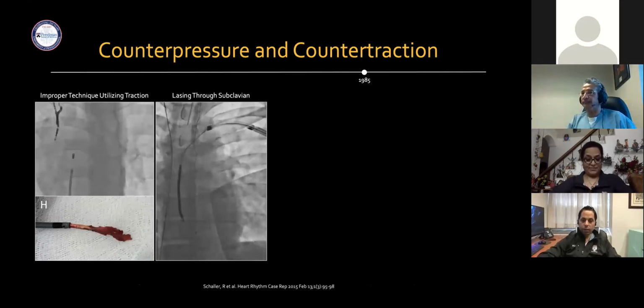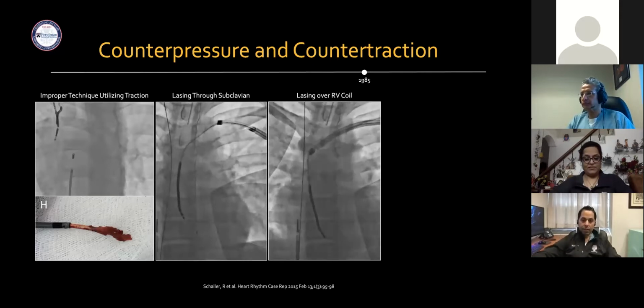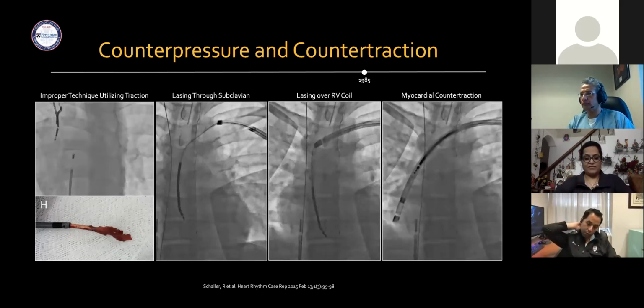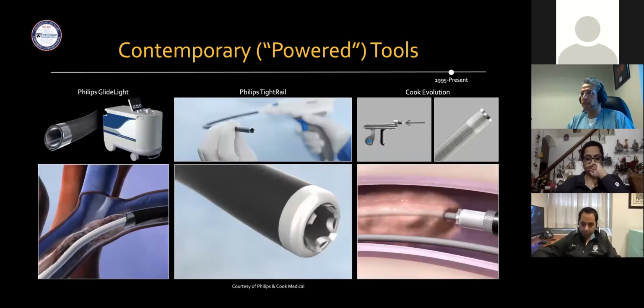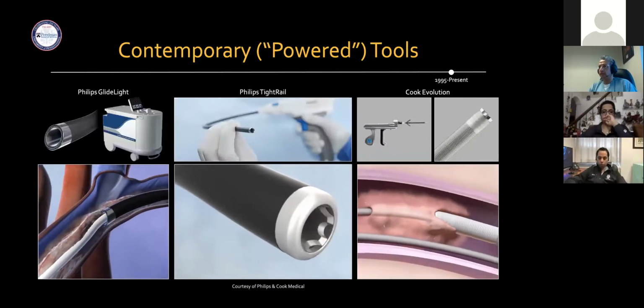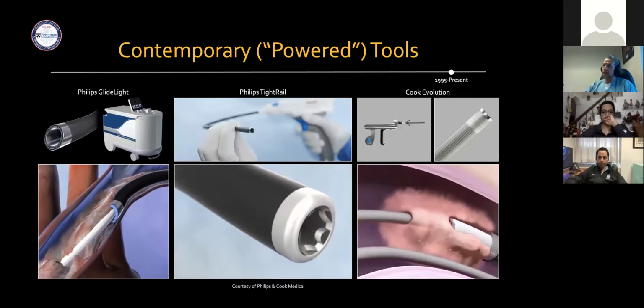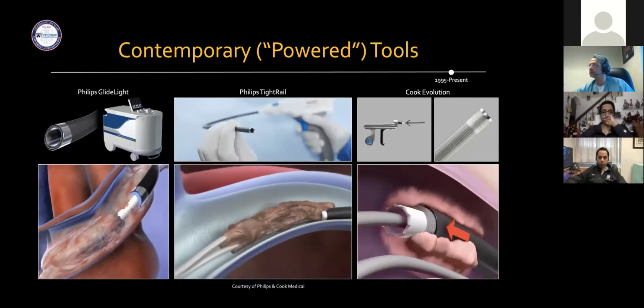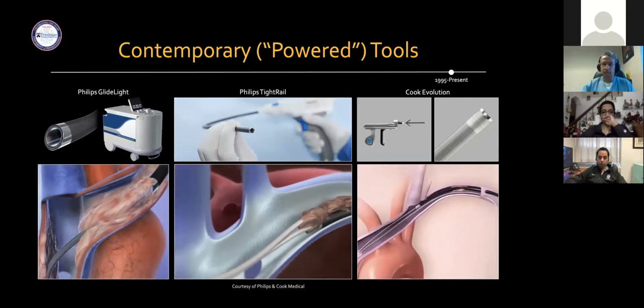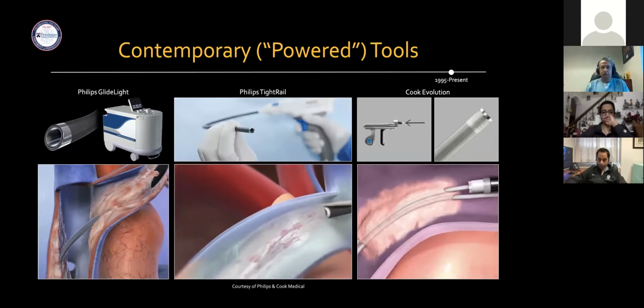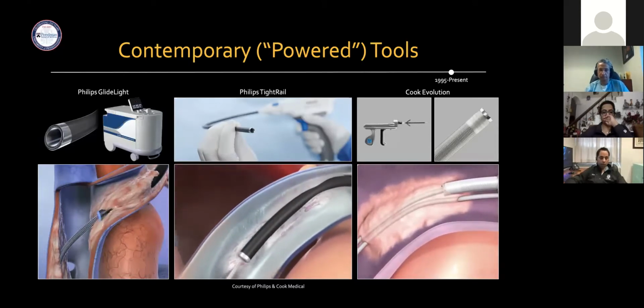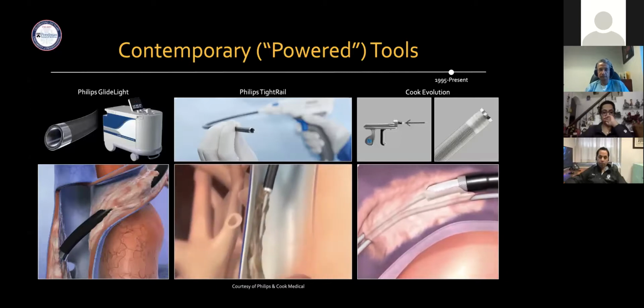And the proper way, of course, to remove the leads in contemporary lead extraction is to try to get the tip of the sheath all the way down the SVC and all the way down to the tip. So the goal of any extraction procedure is to get the tip of the sheath to the tip of the lead. This doesn't always work, but this is in fact the goal. And there are many so-called power tools that you can utilize to aid in the lead removal process by disrupting some of the scar tissue on the myocardium and in the vasculature. I think all of them have pros and cons, and I think they all can be used quite safely if utilized in the proper manner.